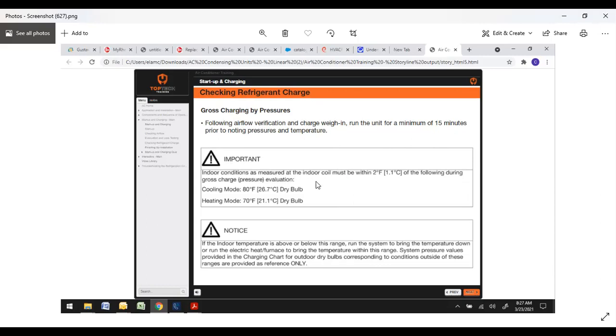Important, indoor conditions. Indoor conditions should be, in cooling mode, around 80 degrees dry bulb, and in heating, 70 degrees. If the indoor temperature is above or below the range, run the system to bring the temperature down, or run the heat to bring the temperature within this range. System pressure values are provided in the chart for outdoor dry bulbs to the corresponding conditions. If you have an indoor temperature of 50 degrees, it's going to be really hard to charge an air conditioner. So kind of bear that in mind. Usually you're going to be realistically anywhere from 70 to 80 degrees typically. So you should be somewhat within the ballpark.